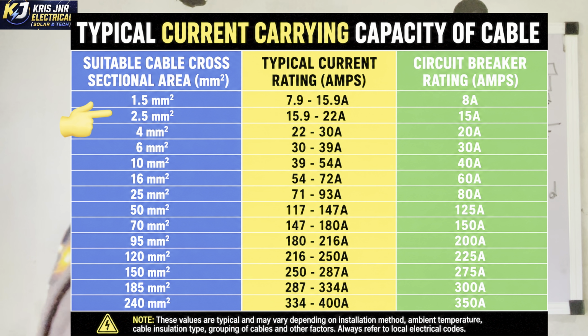So if you make the mistake of using this, most solar installers, I went to do a kind of solar correction, and I saw this. You see videos online where solar installers will use 4 mm. After calculating this 4 mm here, they'll use it to connect everything, including the battery. So imagine using 4 mm to connect a 208 amp battery. Now you are building a fire system. It's not a solar system, it is a fire system.